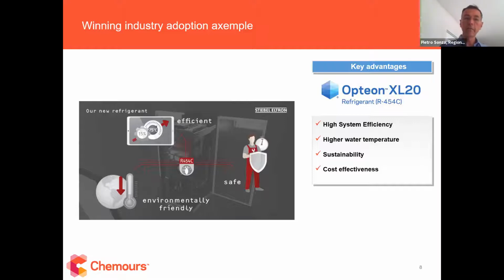The other fantastic achievement is that, through optimization of the system around the thermodynamic properties of 454C, it was possible to achieve a 15% COP improvement versus the baseline—meaning the previous fleet manufactured by the same manufacturer, which was based on R-134A. This is remarkable because at the same time they achieved implementation of a very low GWP solution in a safe manner, with both performance enhancement and end-user benefit improvements.